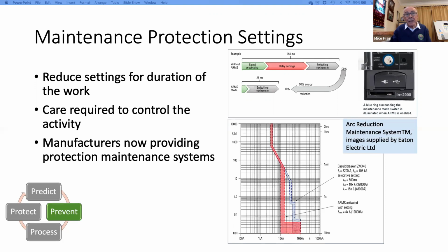Eaton, the manufacturer, recently patented a system that they called Arc Flash Reduction Maintenance System, ARMS for short, and there's images there on the right-hand side showing how it works. Basically at the top there, you've got the front of the protective device, and that setting there sets the maintenance mode for that particular device. What happens in blue there, that's the normal setting for the device. In red, that's a maintenance setting, and it's done roughly what's happened in the previous slides, isn't it? That's something that I think will be quite popular in the future.